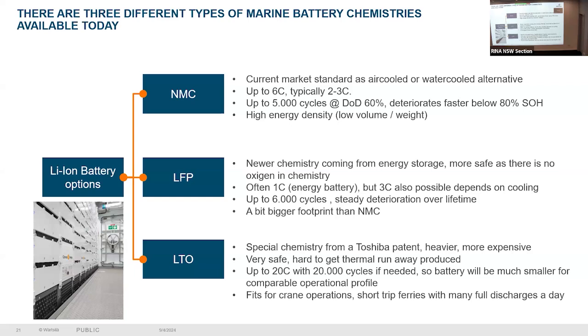One is NMC, nickel, manganese, cobalt. This is one of the most popular batteries as of today because of its power to weight ratio and high energy density. These are available in both options, air-cooled and water-cooled, up to 6C, typically 2 to 3C. It can go up to 5,000 cycles, with a DOD, depth of discharge, of 60%, and deteriorates faster below 80% state of health.